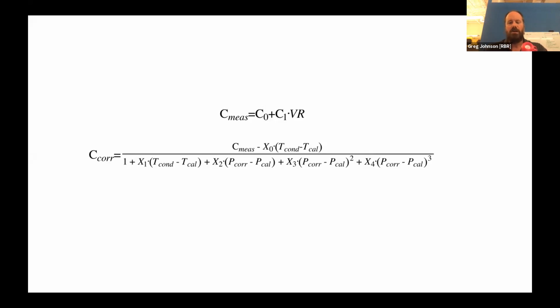On an RBR, it is a combination of that, but we also have a current that circulates around the outside. And so it's a geometric factor that incorporates what might be a very non-primitive geometric shape. Instead of just having a pure cylinder, we've got something that's designed for hydrodynamic flushing, so we don't need a pump at all to get water to move through the cell. It's only about a 4:1 aspect ratio. But we do have a cell that would not be suited to numerically figuring out what the cell constant is.